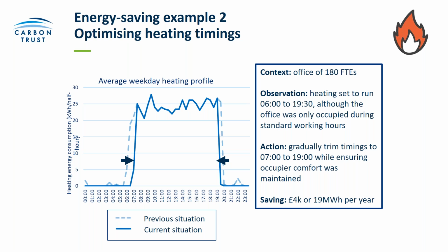So they managed to just trim these heating timings by an hour in the morning. So they had the heating coming on at 7 AM. That still gave it enough time to heat up before anybody started coming into work. And they turned the heating off at 7 PM instead of 7:30. So it's only an hour difference in the morning and half an hour in the evening. But this accounted for a saving to the organisation of £4,000. So even something quite simple as that, with no impact on the staff's comfort, just out of hours heating, they had a saving there. So it's worth checking on your timings.